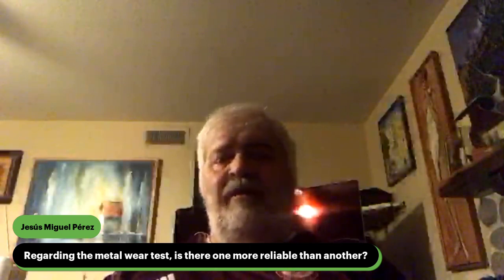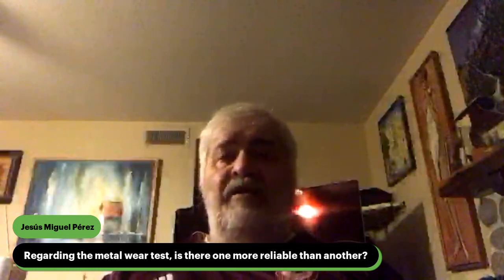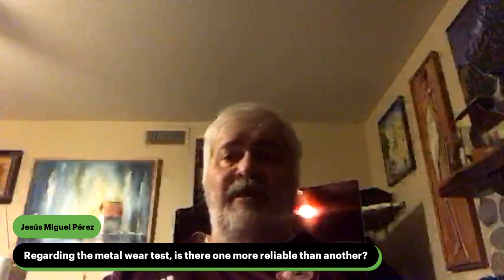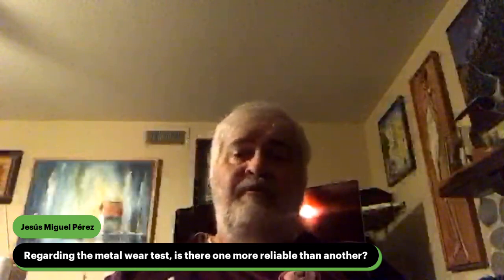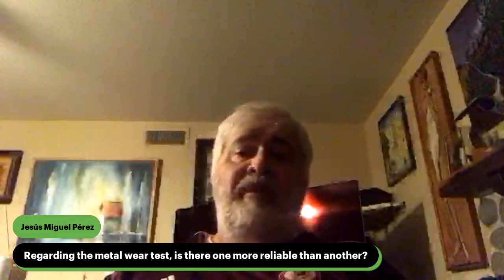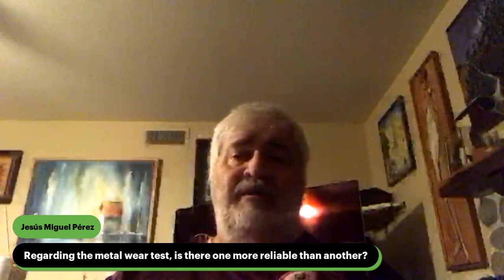So this is actually an interesting question about, is one test method more reliable than the other? It could be in your particular application. So let's talk wear metals, and a gearbox is a good example. If we have an industrial gearbox that has 3 ppm iron, we're probably not going to take action at that type of information. You know, maybe at 40 or 50 we'll do something, or 20 will do something, or 100 will do something, depending upon the system.